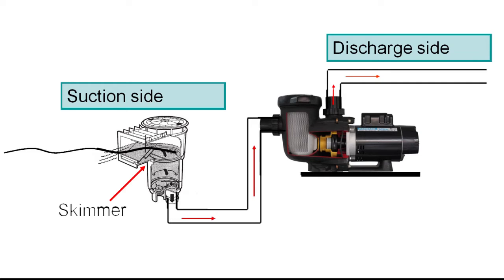Pumps lose prime for many reasons, and the most common are: 1. Water level is too low in the skimmer. 2. The pump pot O-ring that seals the lid goes bad. 3. A valve on the suction side starts sucking air. 4. A threaded fitting starts sucking air.